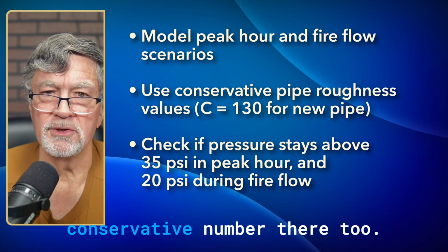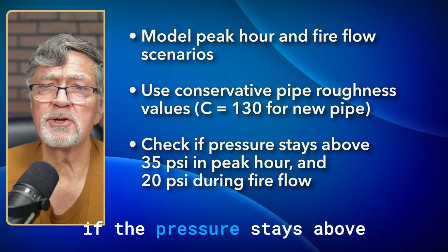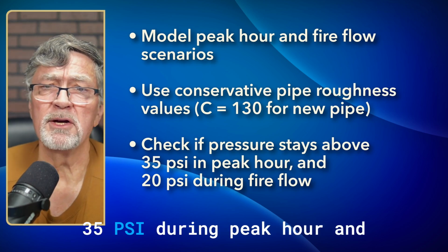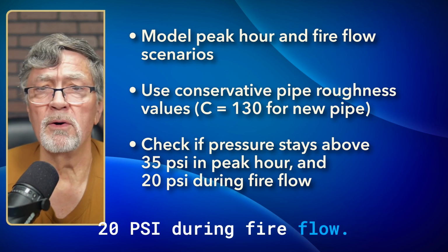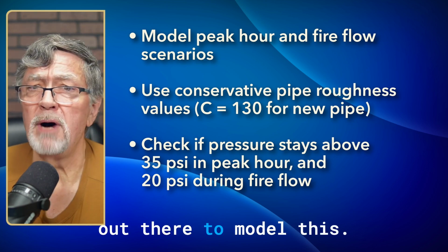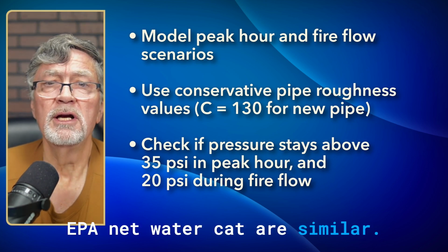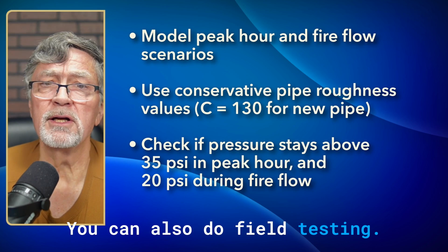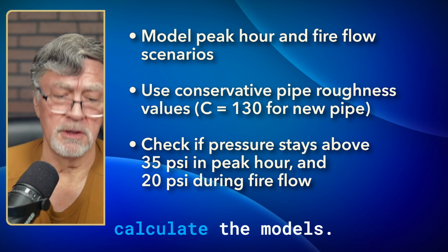So coming up with a conservative number there too. You're going to want to check if the pressure stays above 35 psi during peak hour and 20 psi during fire flow. There are some tools out there to model this, EPANET, WaterCAD, or similar. You can also do field testing, so hydrant fire flows to calculate the models.